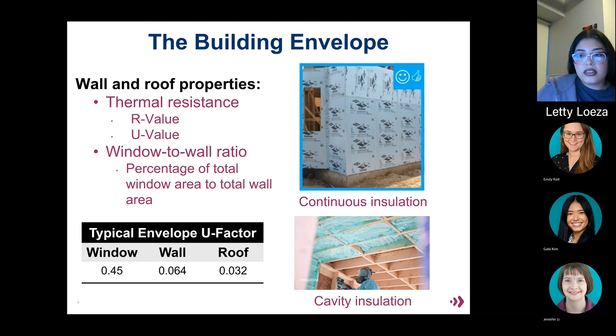The U factor for walls is calculated by using the combination of R values of its continuous insulation and its cavity insulation. Continuous insulation will have a much larger impact overall than cavity insulation will have. Window to wall ratio should also be considered since it ties into both infiltration and thermal resistance. An ideal ratio would be generally 40%. As the window to wall ratio increases, so does the potential for more air leakage and thermal conductance. Even the best performing window can be outperformed by a reasonably constructed wall. Very high window to wall ratios can lead to glare and poor occupant thermal comfort.